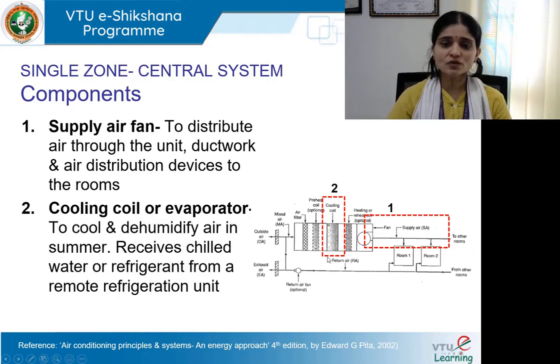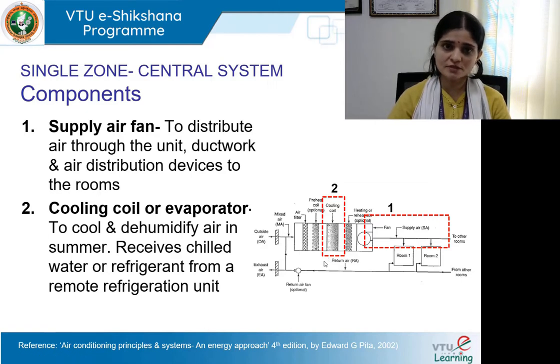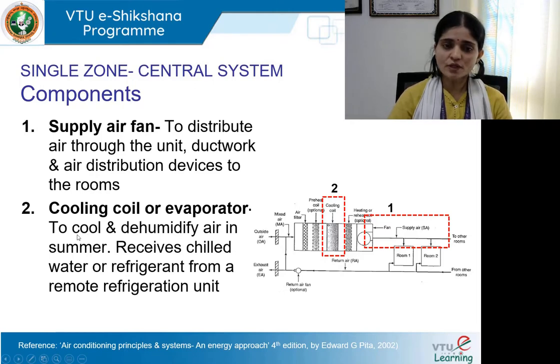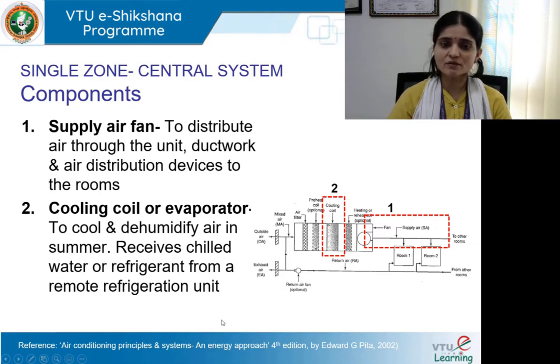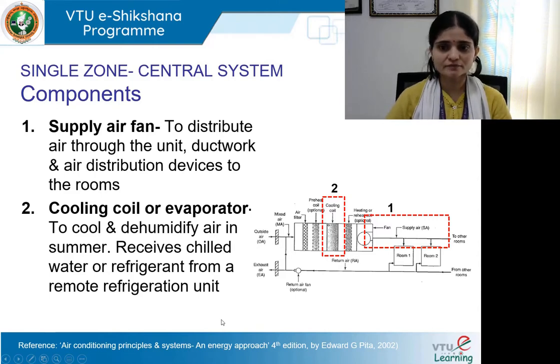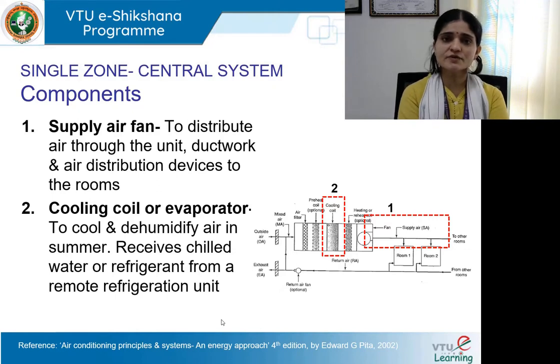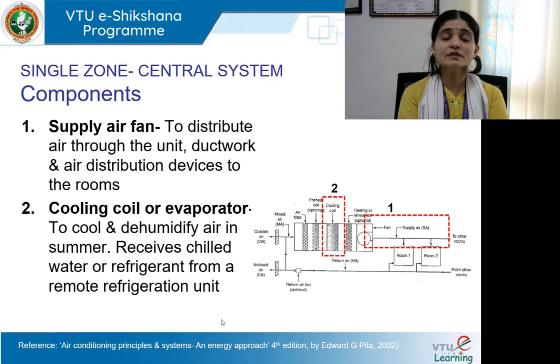Number two: the cooling coil or evaporator — both terms are used synonymously. It is used to cool and dehumidify the air in summer time. It receives chilled water or refrigerant from a remote refrigeration unit. The cooling coil is at the interface between the unit and the room to be cooled, and hot air first enters the evaporator where all the processes initiate.